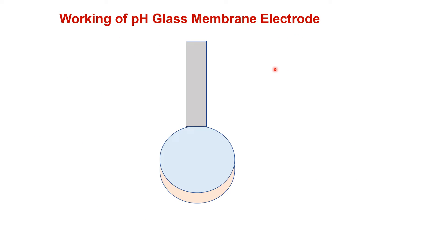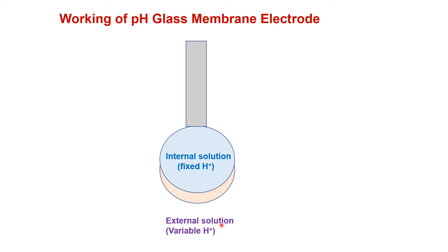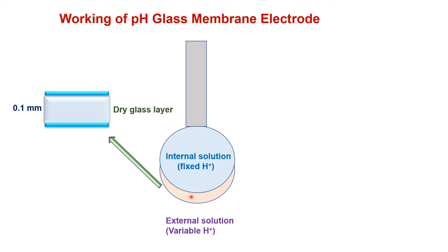The working of the pH glass membrane electrode: the pH value of the solution is related to the hydrogen ion ratio inside the probe and the solution being tested. The internal solution has a fixed hydrogen ion concentration, while the external solution has a variable hydrogen ion concentration. The sensitive area of the pH probe has three regions. The first is the dry glass layer, with thickness 0.1 mm or 10⁵ nm, which has no exchangeable sites for sodium or hydrogen ions — it has fixed sodium ions.